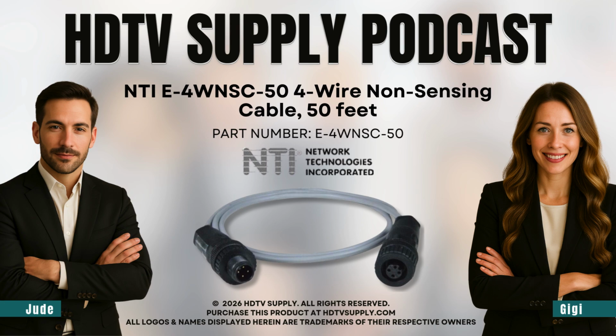So we have a tough, fire-safe locking cable. But let's go back to the non-sensing part. Where does this actually go? Why not just use the sensing cable everywhere? Okay, imagine you run a large facility. You have a server room on the north side and maybe a battery backup room on the south side. You absolutely need leak detection in both of those rooms. Water there is a catastrophe. Right, you need eyes on the prize in those high-risk zones.